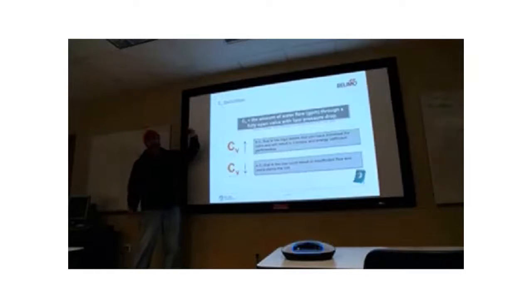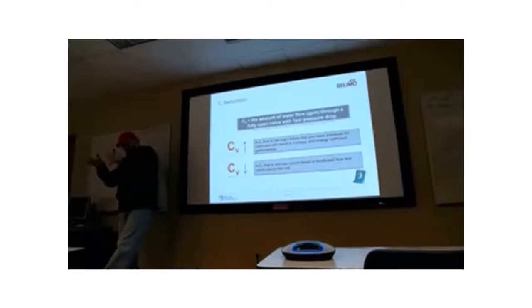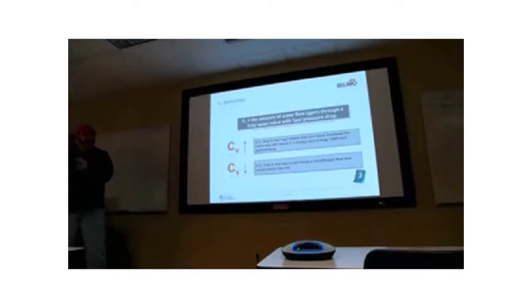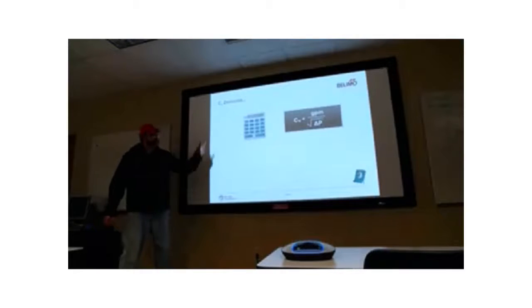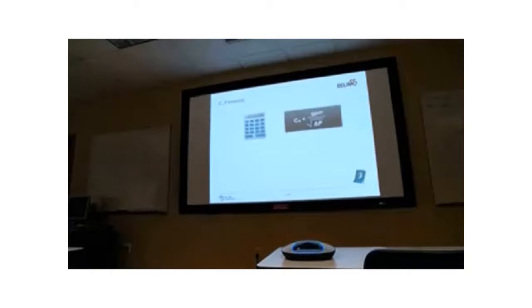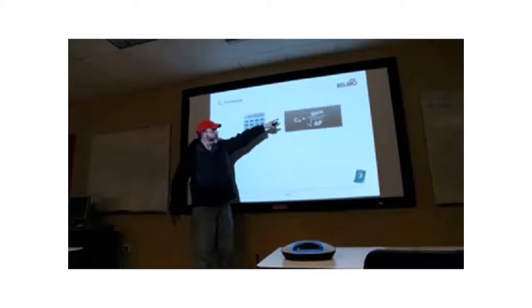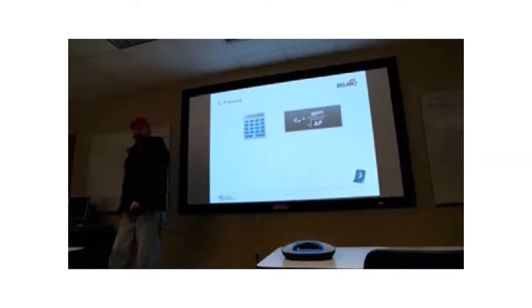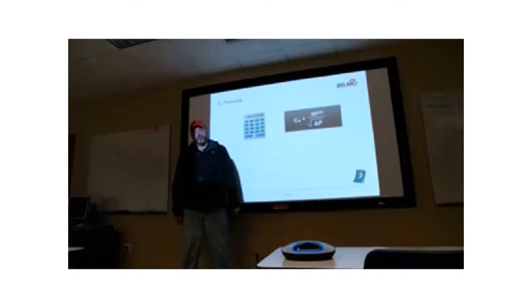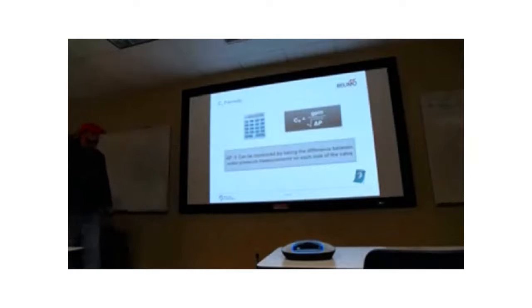So the whole key here with pressure dependent valves is to try to understand what the pressure drop should be based on where it is in the system, and then pick it as close as you can to that. So here's the magic formula. We sort of simplify it for HVAC. You guys won't use it a lot, but it's in your workbook on page 26. So what this means is you take the design flow rate in GPM of the coil, and then you divide it by the square root of the pressure drop across that valve when it's fully open. If you had a manometer, you could go across that valve and measure the difference in pressure when the valve is fully open. We don't always do that, but that's what we call the delta P.